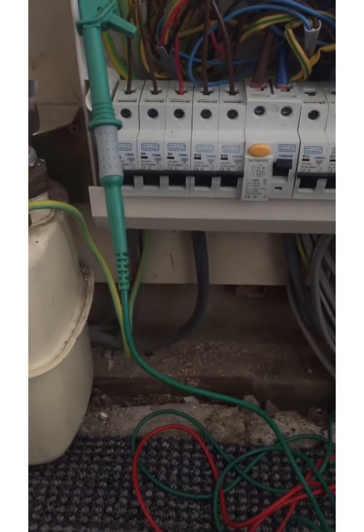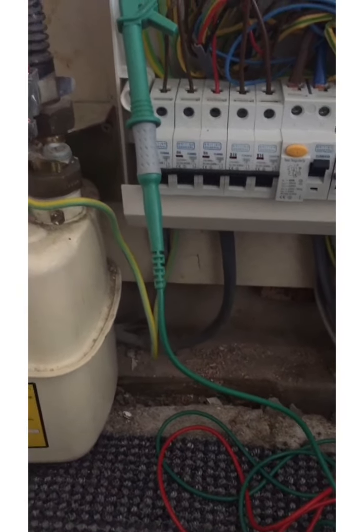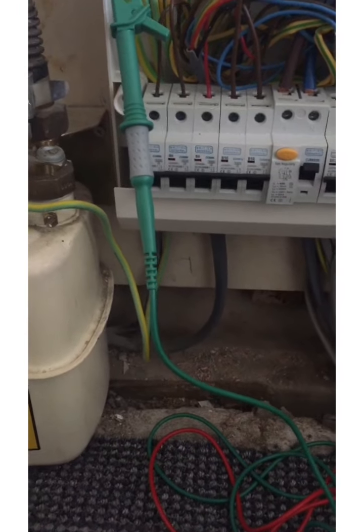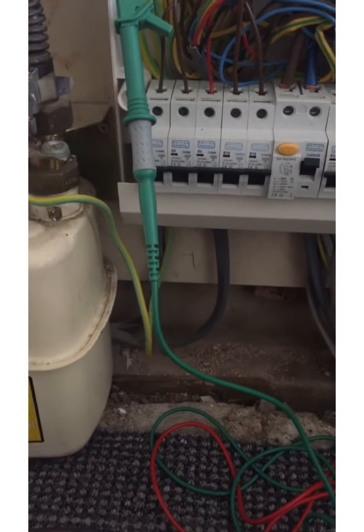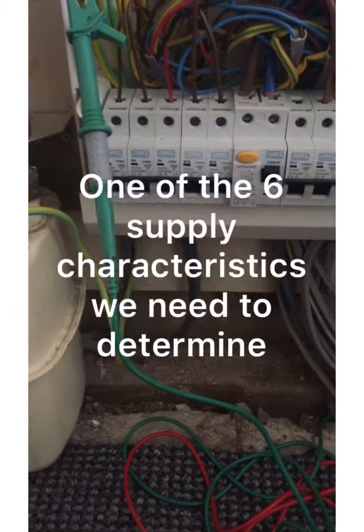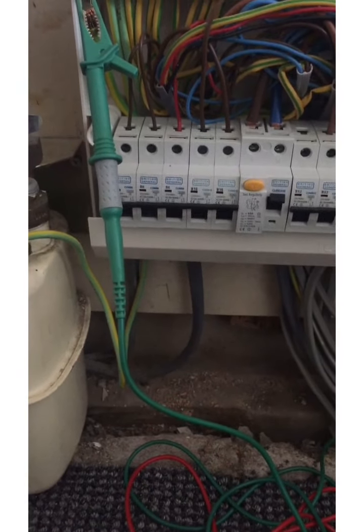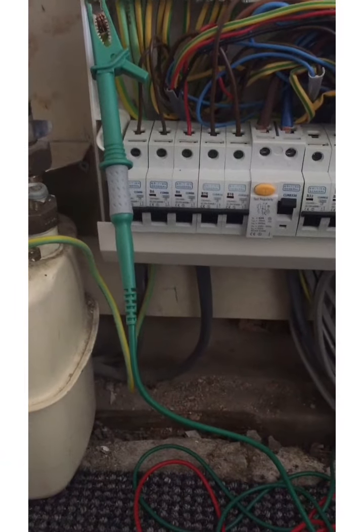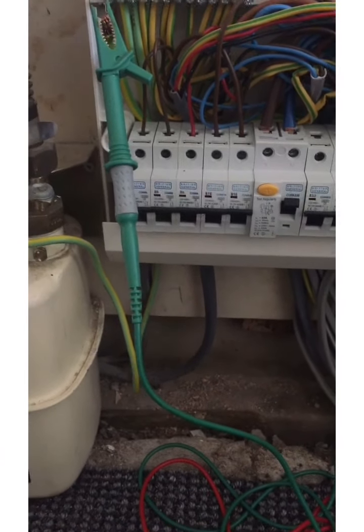Coming today from the isolation wing of Peacock Towers, and I'm going to take you through ZE testing. ZE is your external earth fault loop impedance, which is effectively the impedance of the line and earth back to the substation. The first thing I'm going to emphasize is the fact that it's a live test.